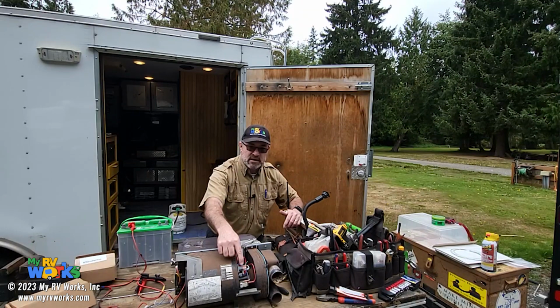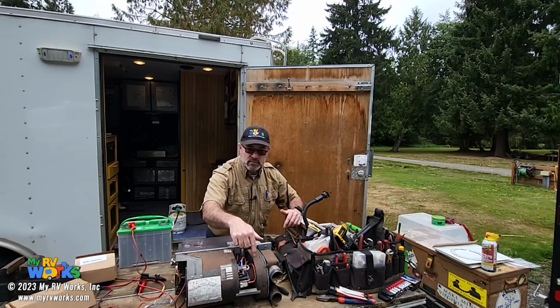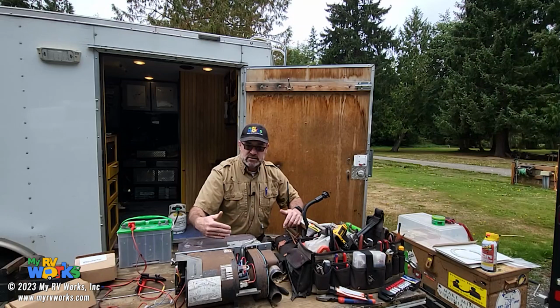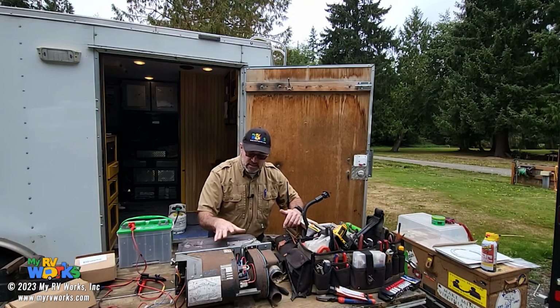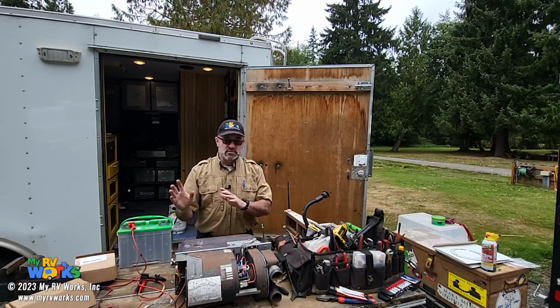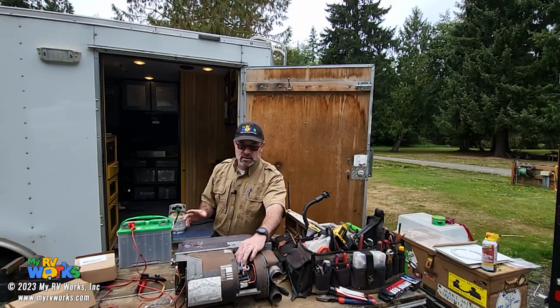I do not have a lot of videos on the furnaces with these older time delay relays on them, so in this video we are going to go pretty deep into the time delay relay, and we're going to be probing the different points on here, and then we're going to be diagnosing what would cause this furnace to have an intermittent fault with extinguishing and igniting. The second part of the video, which will be its own standalone video, is going to be replacing the motor.